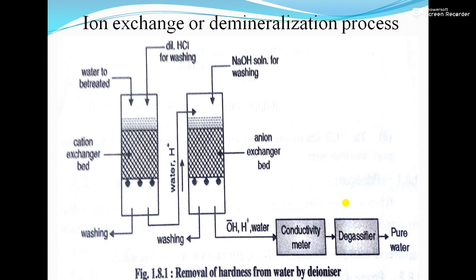In the zeolite process, there is an exchange of only cations. In the ion exchange method, there is an exchange of cations as well as anions. You can see the diagram — this is a cation exchanger resin or bead, and this is an anion exchanger resin or bead. Water coming in here has only cations exchanged, and then water goes to the anion exchanger bead where anions get exchanged. So here only cations will exchange, and here only anions will exchange.